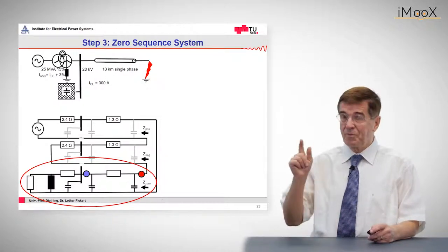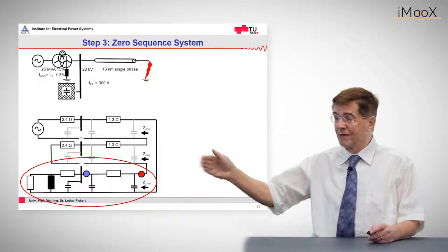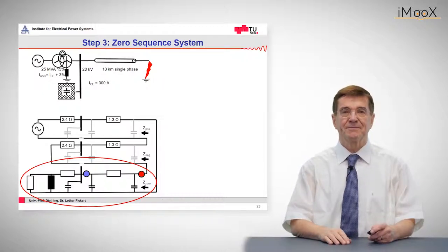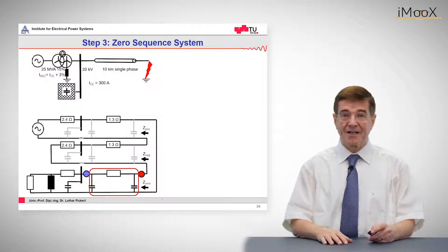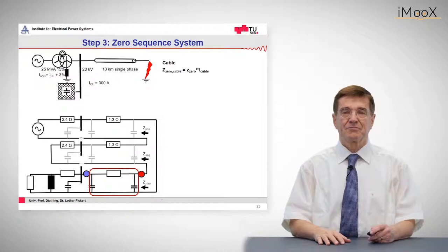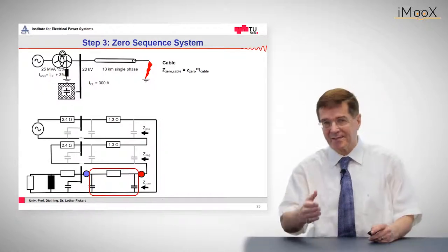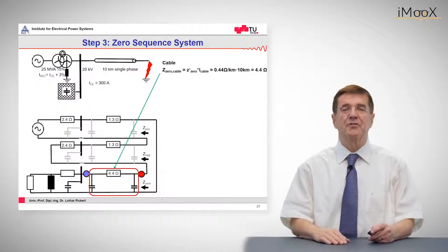Of further interest will be two points. The red one is the fault point and the blue one, further to the left, is the relay location. Now let's see what is the zero impedance of the cable. So the zero impedance of the cable is given by this well-known formula, specific impedance times line length, and that comes out in this case as 4.4 ohms.